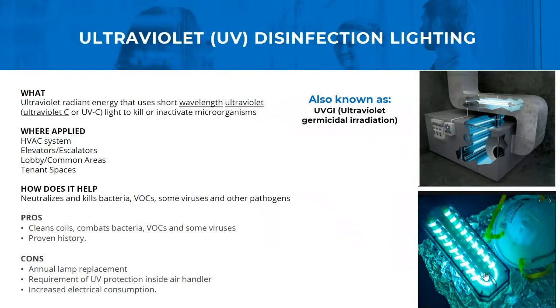Next is ultraviolet disinfection lighting. It goes by many different names: UVC, UVGI. If you see UVGI, it's ultraviolet germicidal irradiation. And what it is, in layman's terms, is ultraviolet radiant energy that uses short wavelengths within 200 and 280 nm that act to kill off or inactivate any microorganisms that pass through the spectrum. This comes into play with HVAC systems, escalators, elevators, lobby and common areas. The longer the air can sit, or the device will sit in front of a bacteria-ridden place, the better it neutralizes and kills those bacteria, kills off the VOCs, some viruses, and has been known to kill off pathogens.